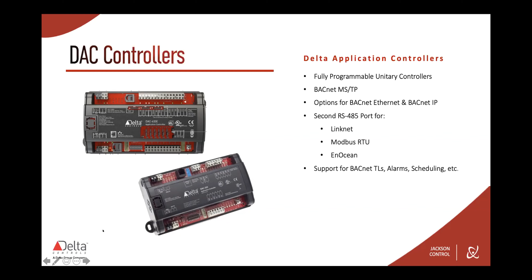So the DVC is essentially the same thing, same firmware files as the DAC versions. The only difference is that they are built more specifically for VAV applications. So they have an onboard flow sensor. They have an onboard actuator. You can order it with or without actuator. So if you want to reuse existing actuators in the field, that's no problem as well. We have options for Belimo and Siemens.